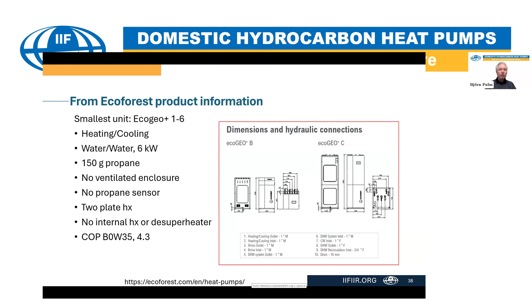Of course, you could imagine that the COP could be slightly higher if we would allow ourselves to have an internal heat exchanger or a desuperheater, and also if we had a couple more plates in the plate heat exchangers. But still, comparing the performance of this unit with those of larger charge, the difference is very small.